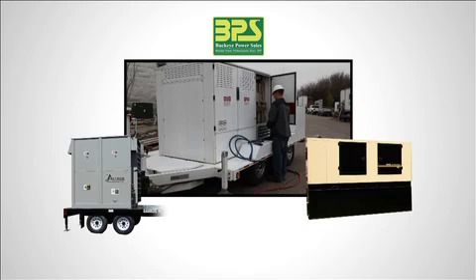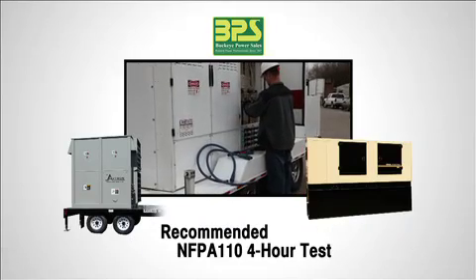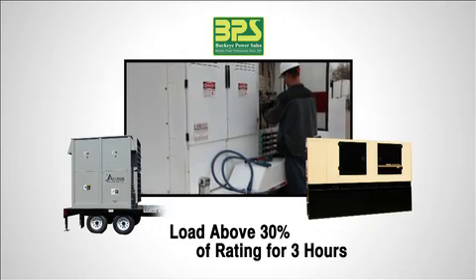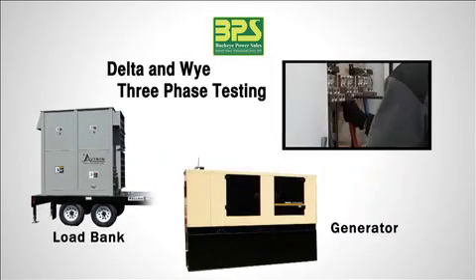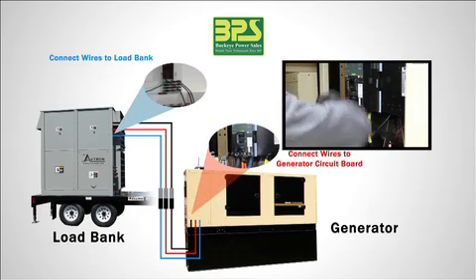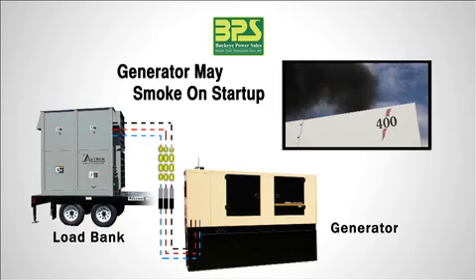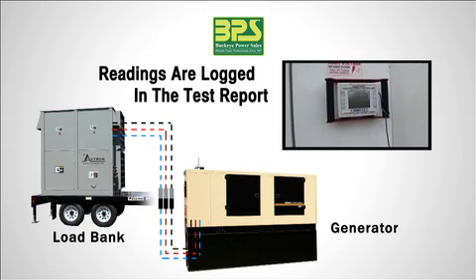Load banking can be part of the usual planned maintenance contract. Our technicians carry out the recommended NFPA 110 four-hour test, which calls for a load of at least 30% of rating for three hours and above 70% rating for an additional one hour. Our technician first connects the wires to the load bank, then connects the wires to the generator circuit board. The generator set is then started, and quite often a set that has not been loaded on prior runs will smoke on start. The technician records the readings, verifies the set is performing as it is meant to, and logs it in the report, referencing the hours that have passed.